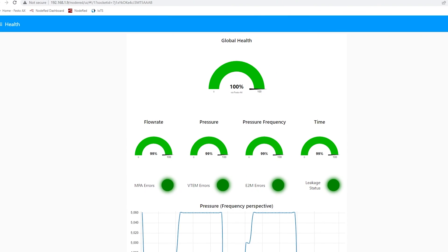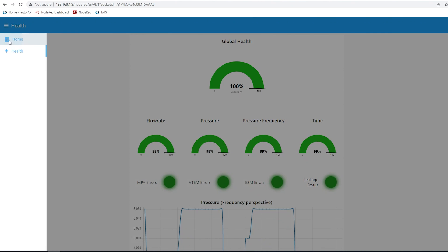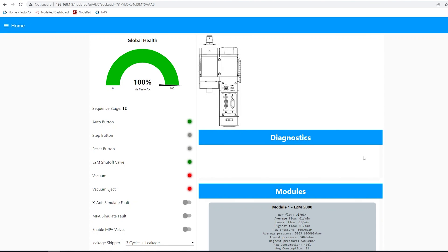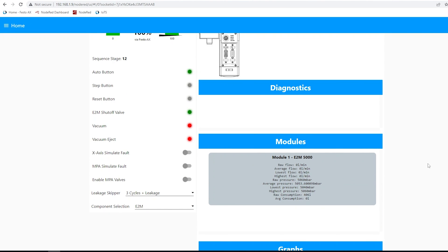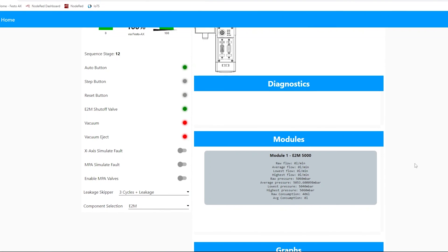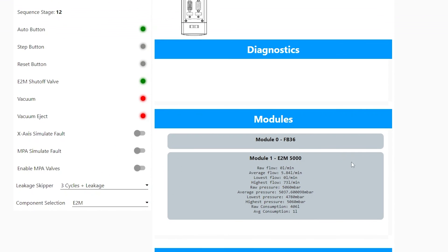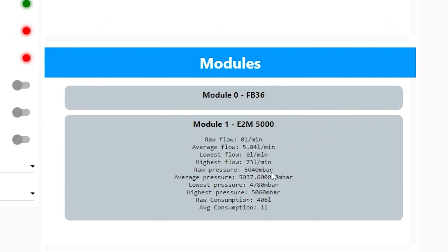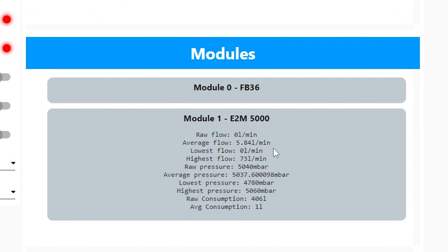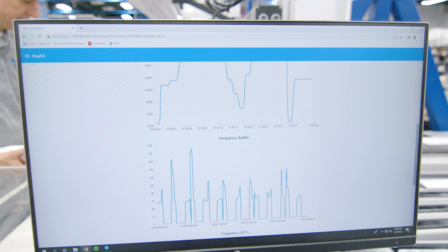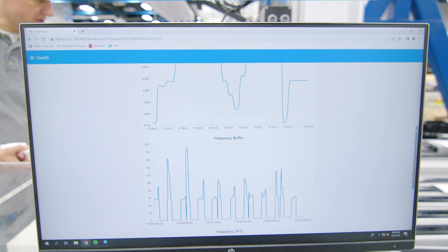So this is a global health value, and if we come back to the AX dashboards, all that data is coming from AX AI software. We should start to see a degradation in some of these performance values because now the system is going to detect an anomaly in the pressure train, in the signature response of the pressure signal.